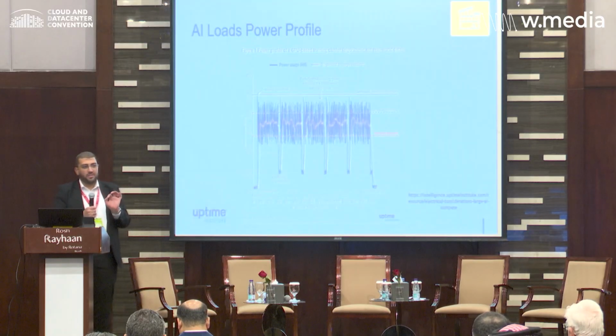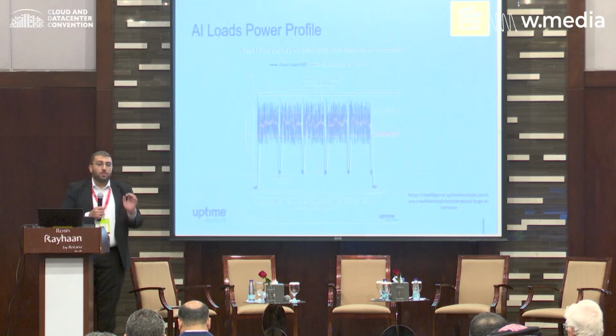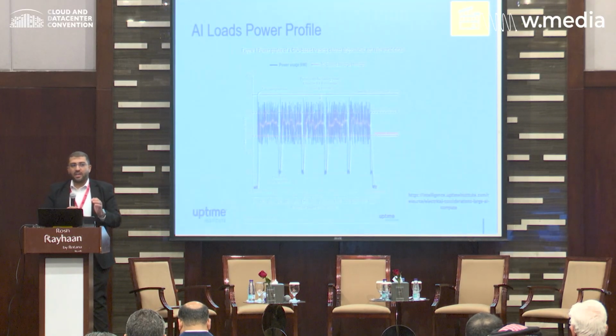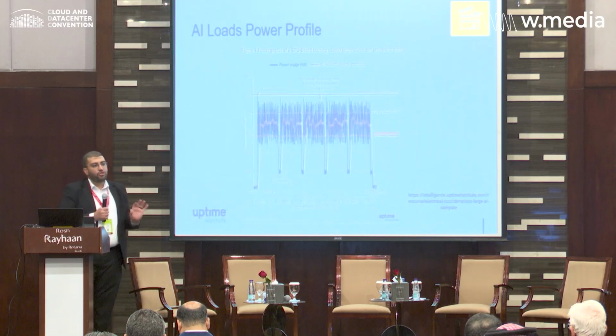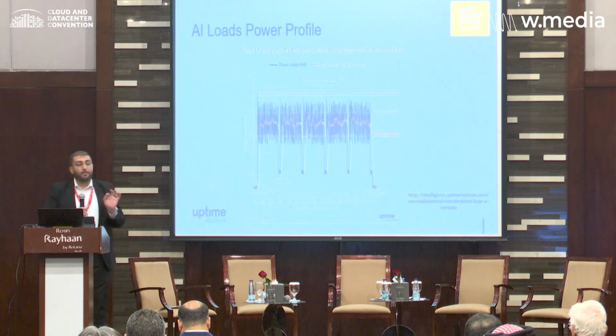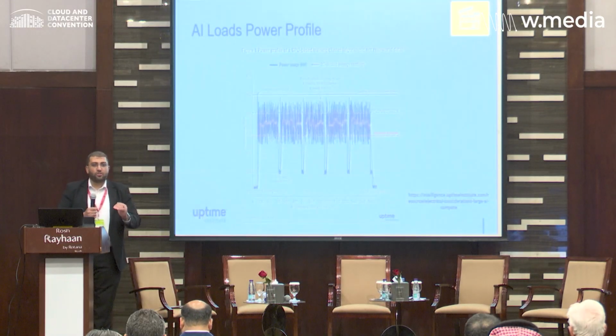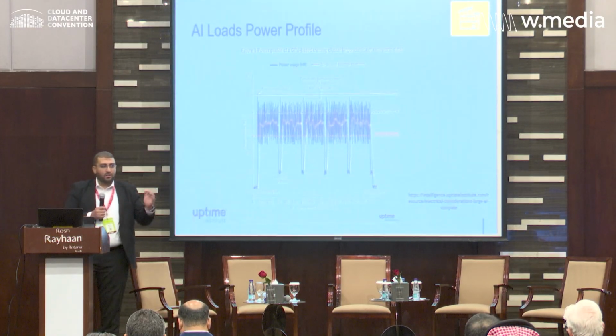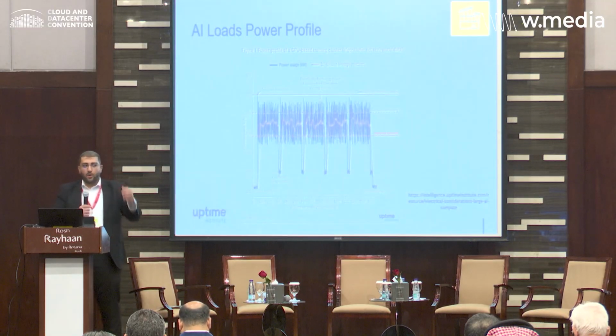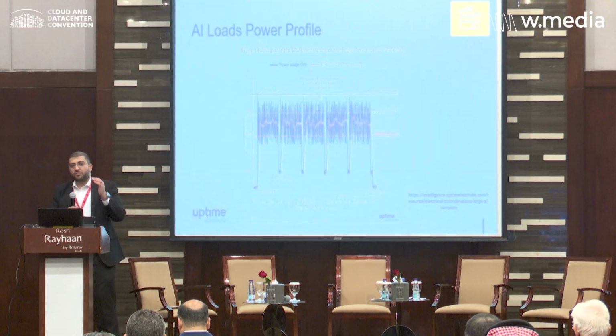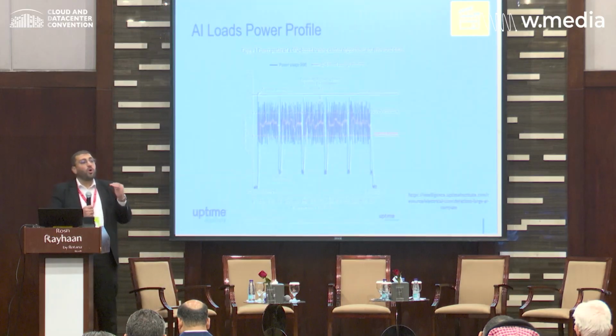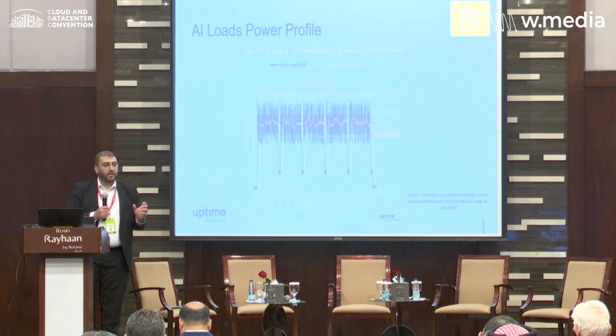If those transients propagate from the IT racks, the AI racks, up to the engine generators, for sure it will impact the engine generators, and for sure it will impact the grid stability. Imagine a 100 megawatt or 60 megawatt AI factory, then you have the transient between 30% to 100% in a few seconds.